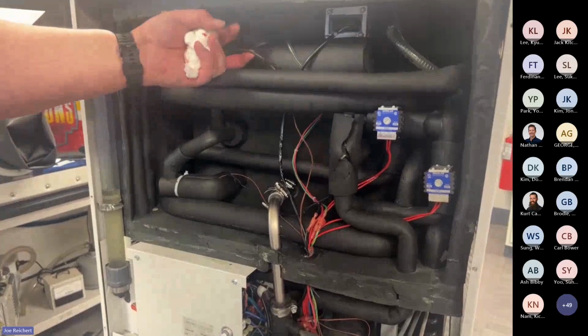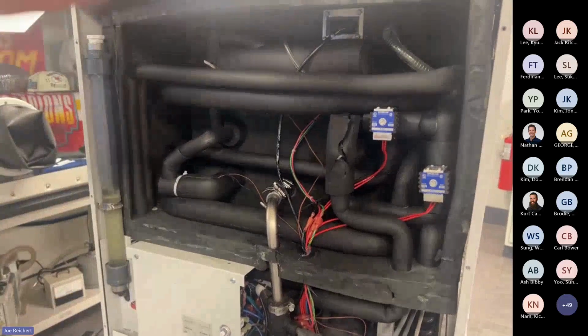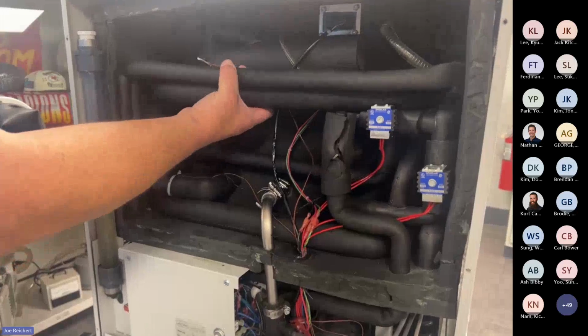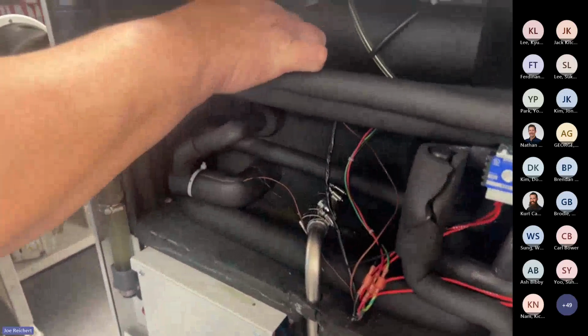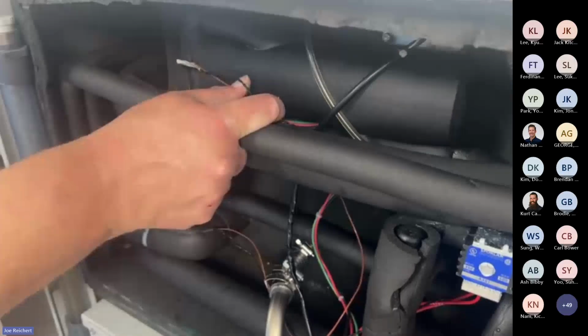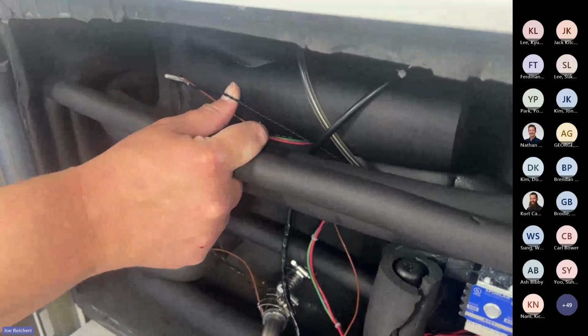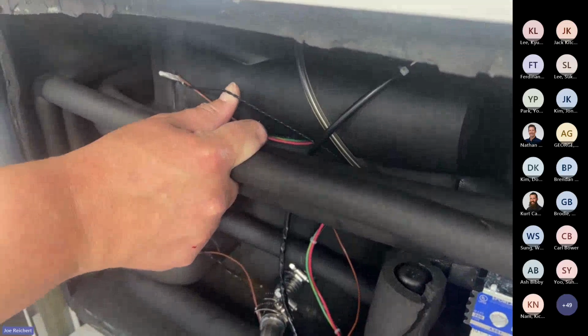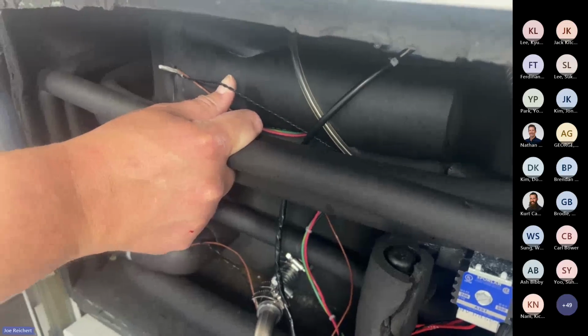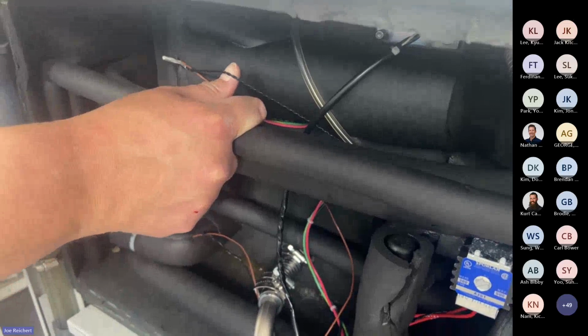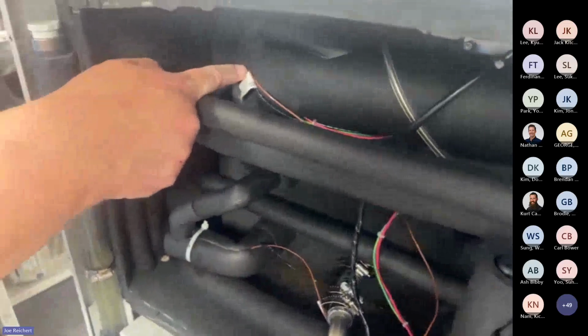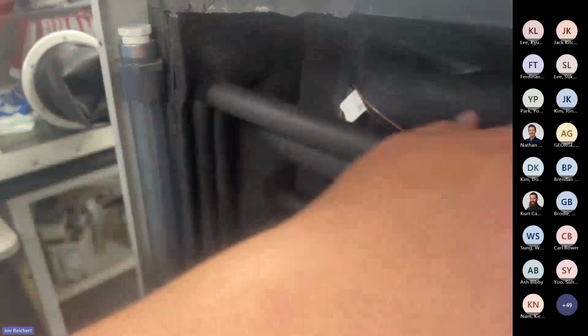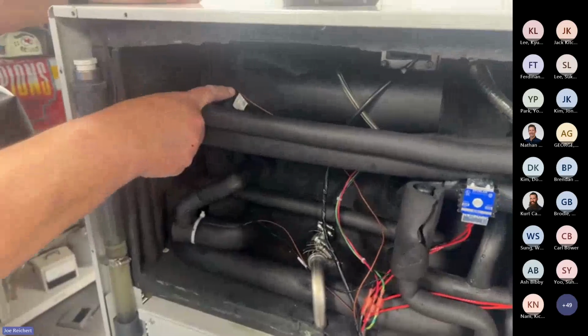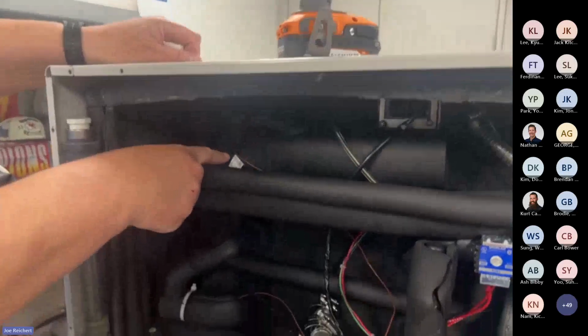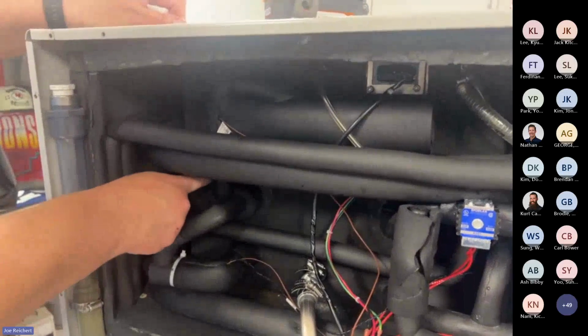The black wire here, this is the wire that I was referring to as the temperature sensor. All of our units use the same type of temperature sensor. It's an RTD, 1000 ohm RTD, but it's always this black braided cable. And this is where the temperature probe actually is. It's right on the Lexol line. This is the heater right here, and then your temperature sensor is right on the Lexol line. It's coming out of the heater and then goes right into the shelf.